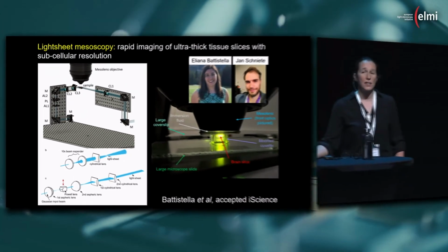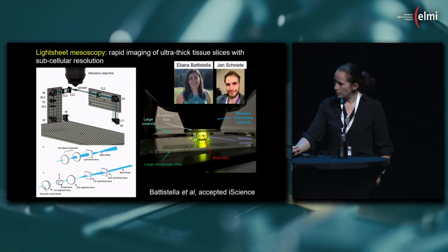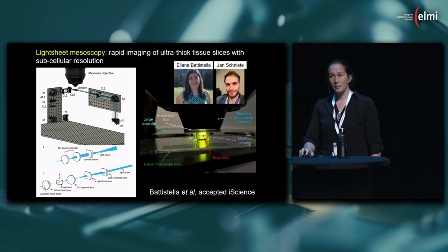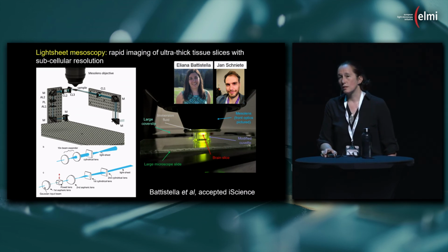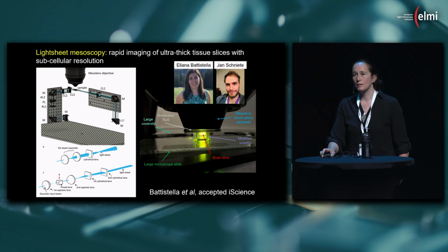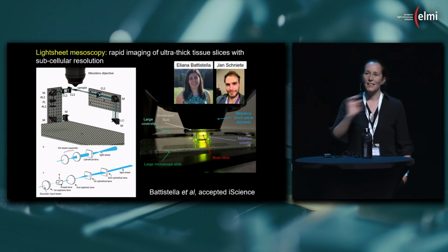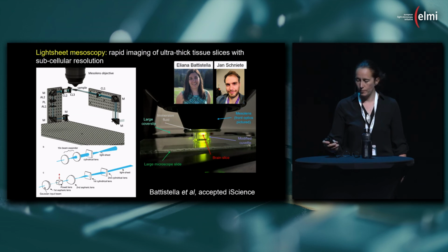So what we did was we built 2 light sheets, one of which is the Gaussian one that I've just told you about, and it turns out it's quite good for fast screening of large samples. And a second propagation invariant light sheet, which uses a Powell lens that's been placed in an off-axis position, shown by this red arrow here, and a combination of this offset in optical path with aspheric elements has produced a light sheet that's more than 4 millimeters long, that's around 8 microns thick consistently across that propagation length.